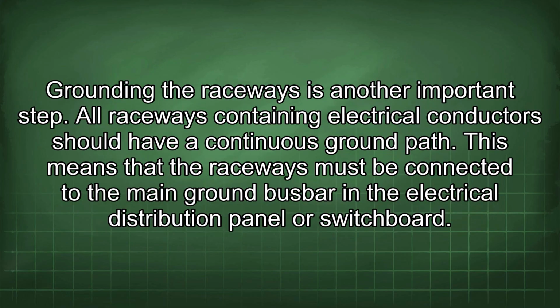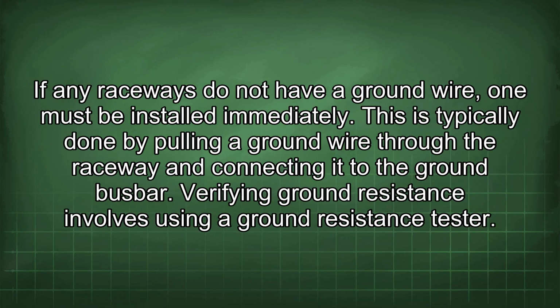Grounding the raceways is another important step. All raceways containing electrical conductors should have a continuous ground path. This means that the raceways must be connected to the main ground busbar in the electrical distribution panel or switchboard. If any raceways do not have a ground wire, one must be installed immediately. This is typically done by pulling a ground wire through the raceway and connecting it to the ground busbar.